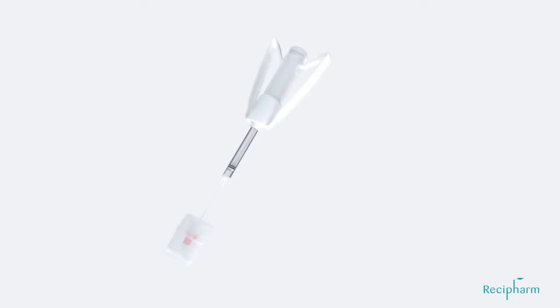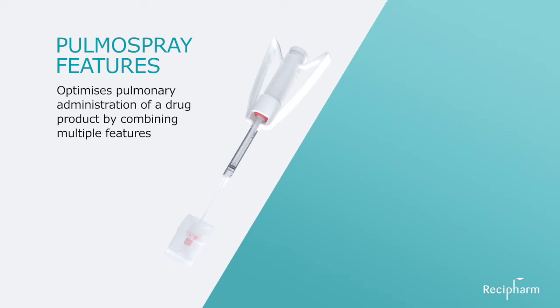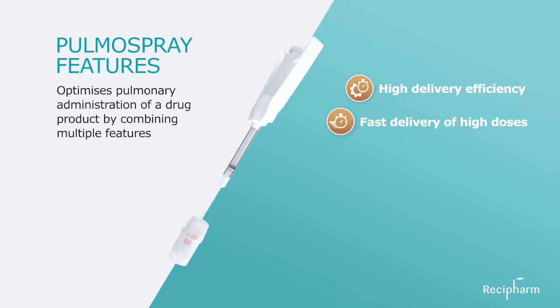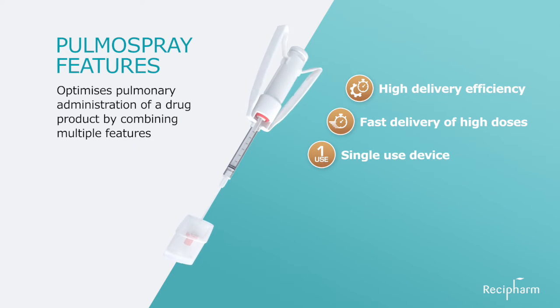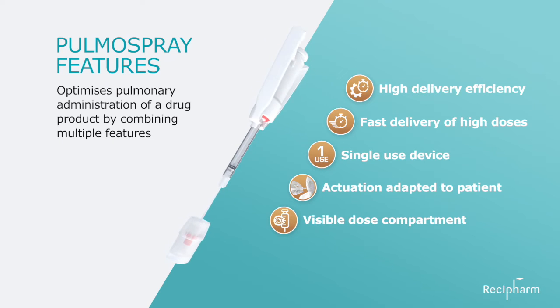The Pulmospray optimizes pulmonary administration of a drug product by combining multiple features. It has a high delivery efficiency due to generation of small droplets and a high resistance to flow, lowering inspiratory flow rate. It is capable of administrating high doses of inhalation solutions in a short period of time. It is a single-use device, so cleaning procedures are not required. Actuation can be adapted to the inhalation maneuver of the patient. The inhaler provides confidence that the medication has been taken in its entirety, as the dose compartment is visible.